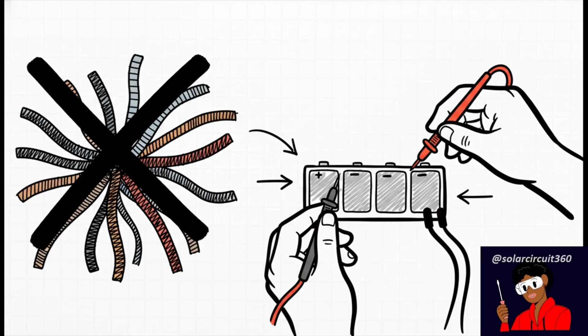Your only absolute certainty comes from taking a digital multimeter and verifying every single connection yourself. And while you're poking around with that multimeter, remember the intense amount of power you're working with here. Dropping a metal wrench or screwdriver across exposed battery terminals will instantly create an extremely high fault current. We're talking about a blinding arc flash, a very serious fire risk, and terrible, severe burns. Always use insulated tools, take off any metal rings or watches, and plan every physical movement deliberately. Never rush your battery assembly. It's just not worth it.